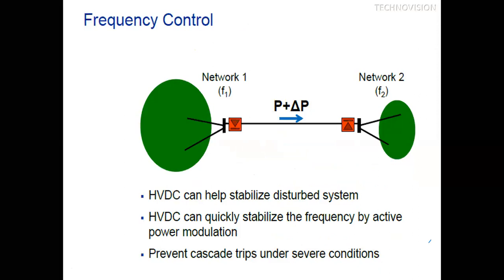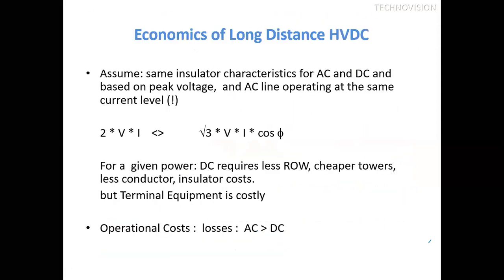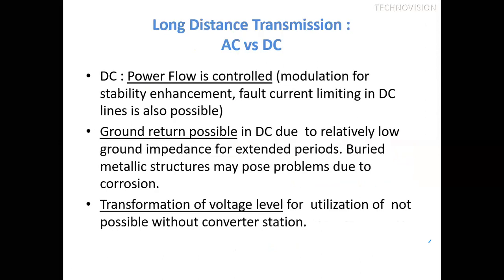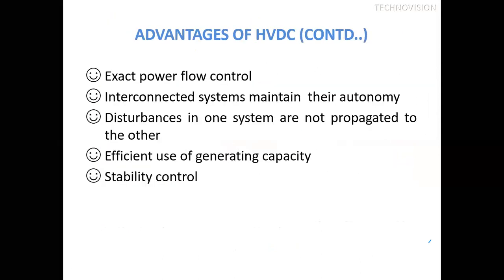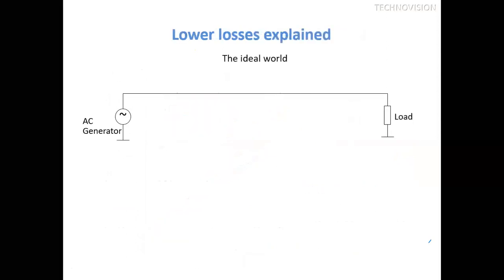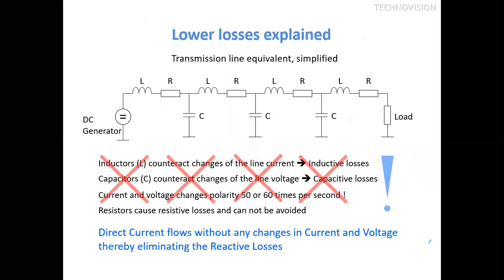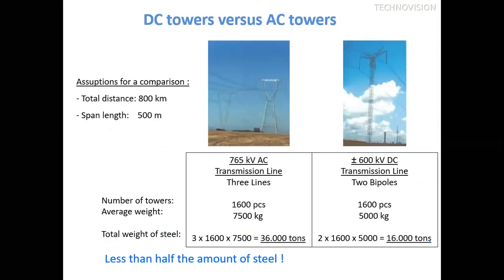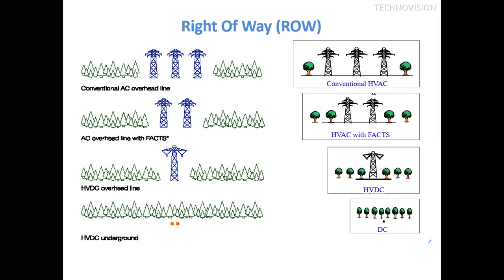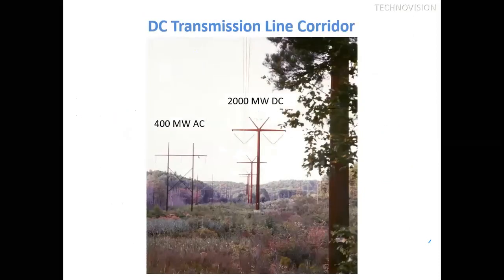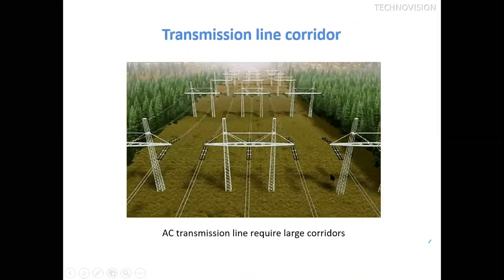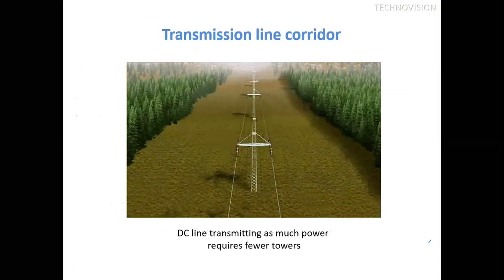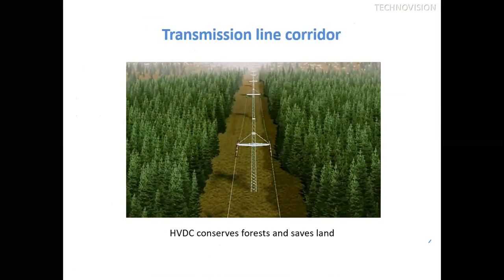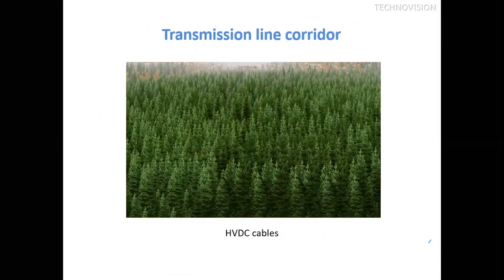There are runback function, damping controller, frequency control. There are many features in HVDC. Ground return, many advantages are there. Lower losses are there in case of DC transmission. When we compare AC and DC, the material cost is very less. Right of way required is very less when we go for DC. We can compare 400 megawatt AC and 2000 megawatt DC in terms of right of way. This is an animation which shows how we can save the corridor when we go for DC transmission. And sometimes when we go underground, there is no issue of corridor either.